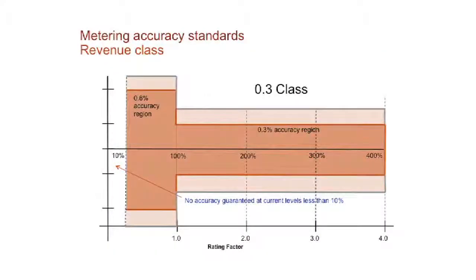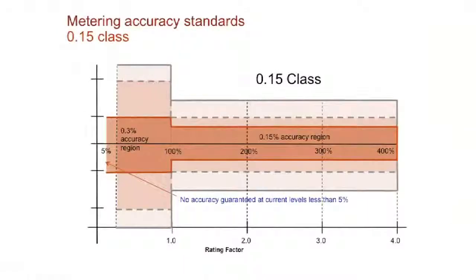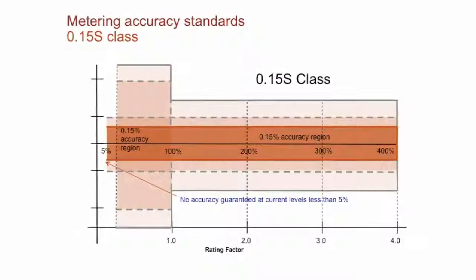The one that most utilities are familiar with is what we call revenue class metering accuracy, or 0.3%. So in terms of percentages, your current accuracy would have to be measured between 99.7% and 100.3%, all along the scale of the current transformer. Because there's been some significant increases in technology with different metals being used for current transformers, there's also been developed a 0.15 and a 0.15 S class. The 0.15 is what we call high accuracy, and then we have a special high accuracy. And we'll go in depth into what those mean now.